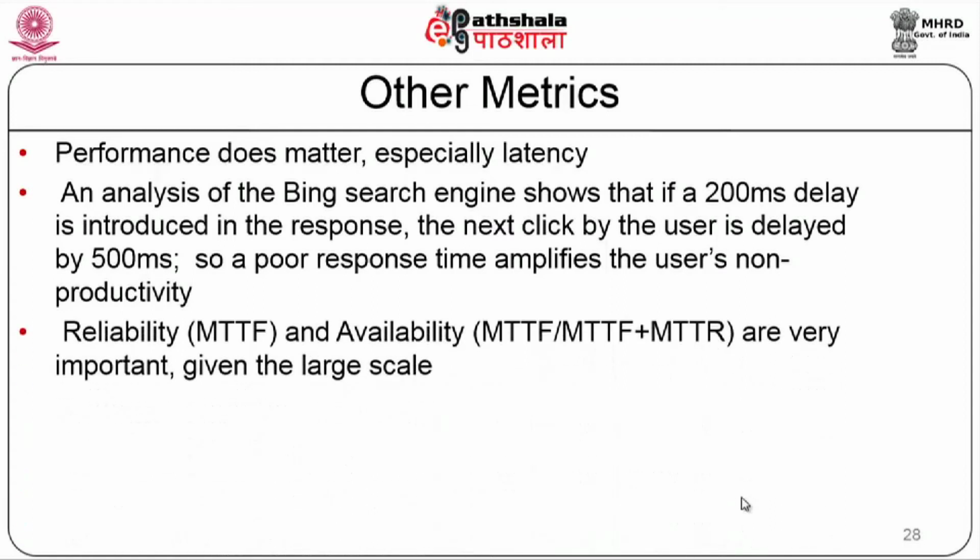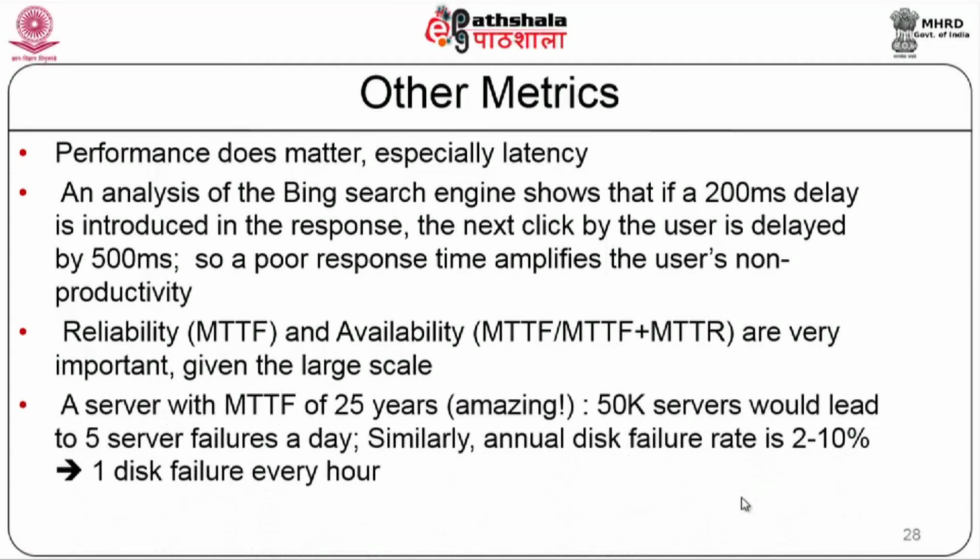Reliability and availability are very important given the large scale of WSCs. Even a server with an MTTF of 25 years, with 50K servers, will lead to about 5 server failures a day. Similarly, the annual disk failure rate is 2 to 10%, which means there will be one disk failure happening every hour. You cannot avoid these failures because of the volumes involved. You will have to take care of it only by redundancy.